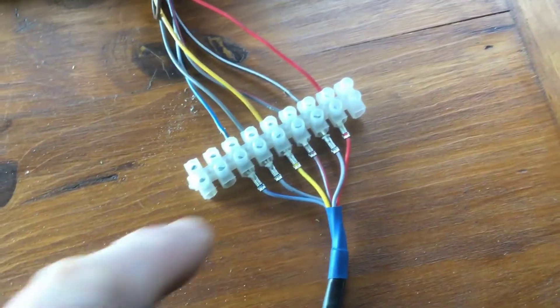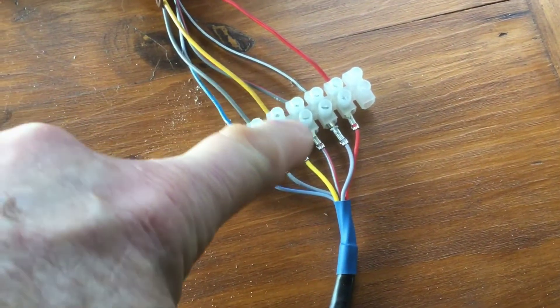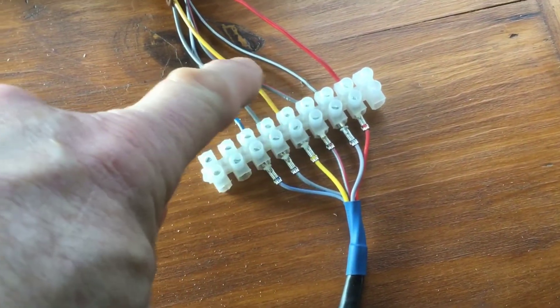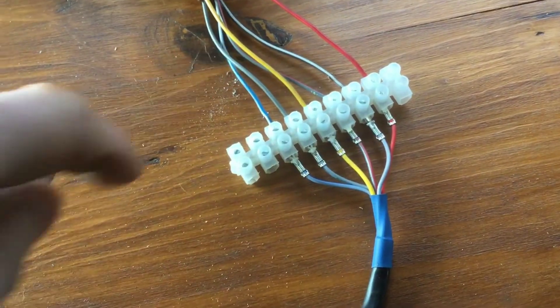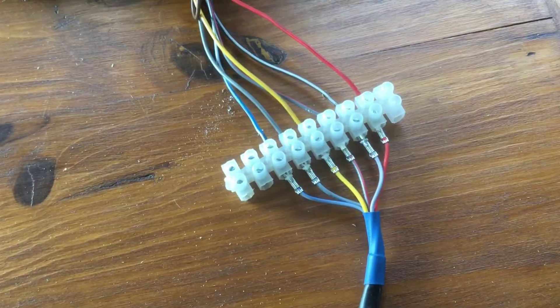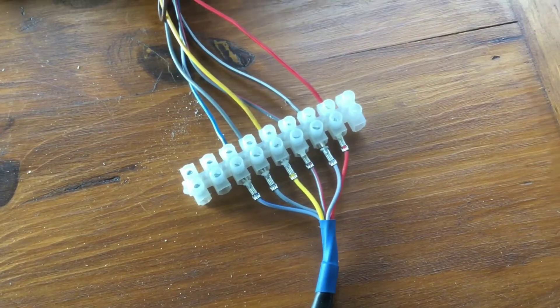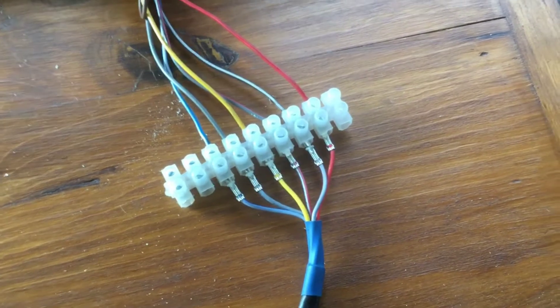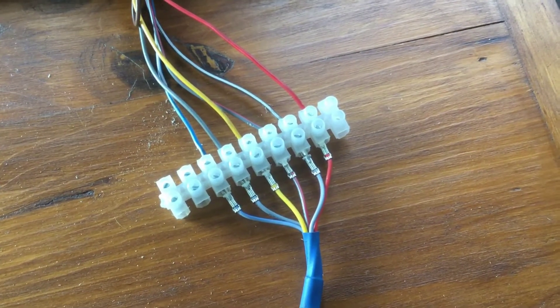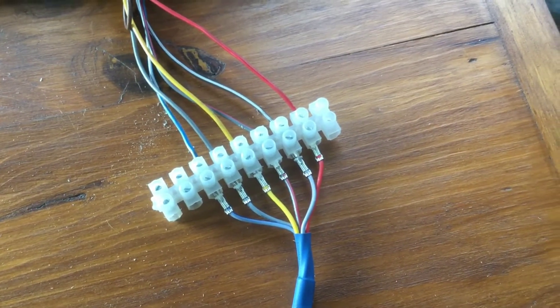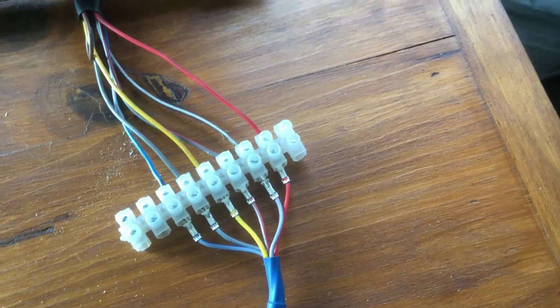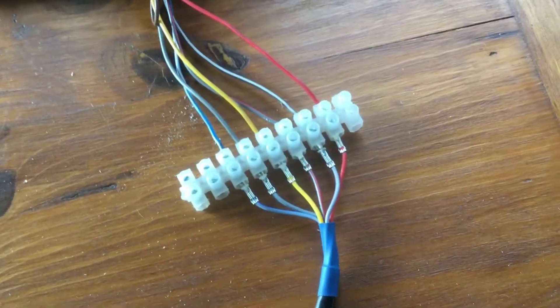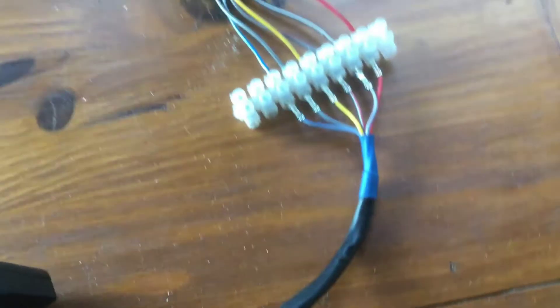Then this one here is a brown and white wire. This is the reference earth that's used by the controller and the heater. It's an internal earth. It's just a clean earth supply basically. And the last wire is 12 volts. That's the power from the heater that actually powers the controller up and hence the display works, etc.